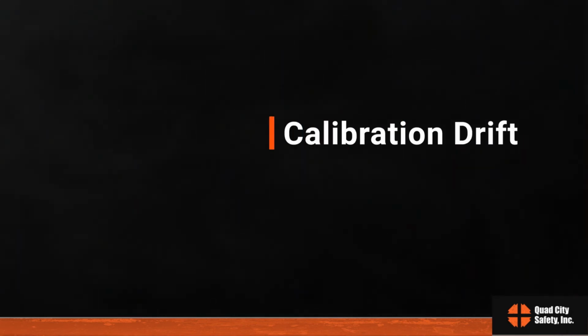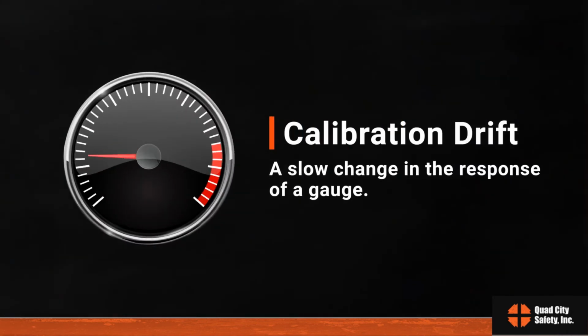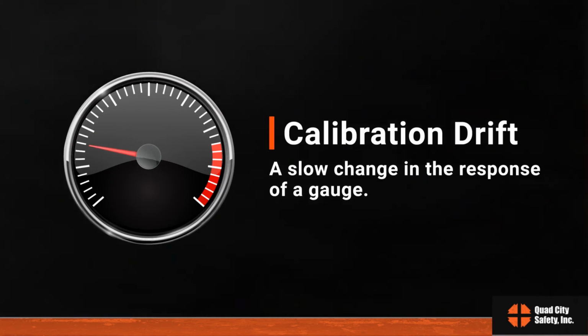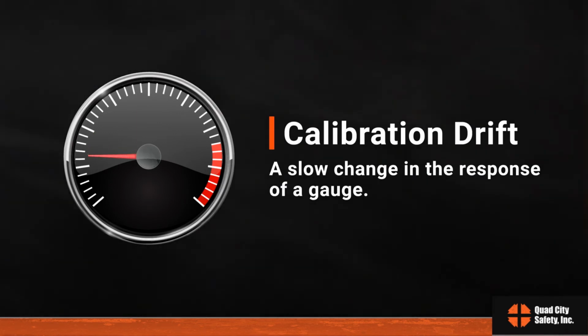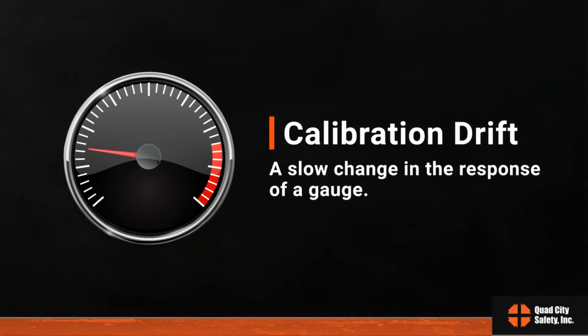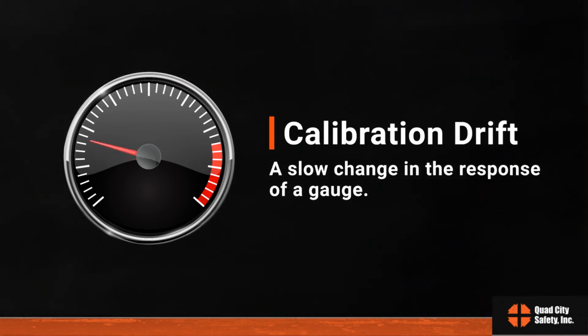Be aware of calibration drift. This is common due to the often volatile conditions of the site. Calibration is a critical part of maintenance and should be checked to be certain that the instrument's measuring accuracy is relative to the traceable concentration of the test gas. Without this key step, you're flying blind.